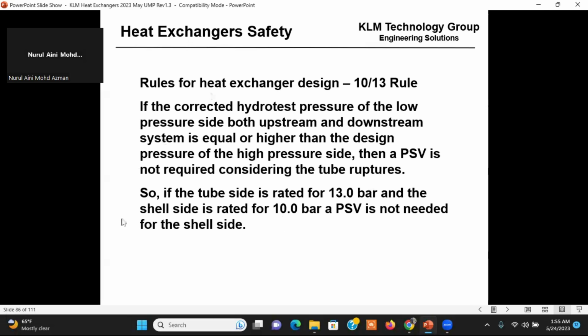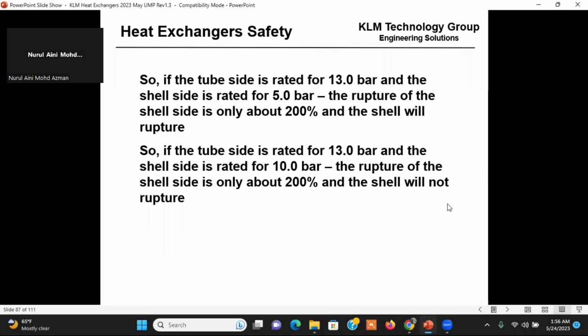Okay. So in general, I always try to follow the 10/13 rule, where if the tube side's rated for 13 bar, the shell side's rated for 10 bar. All right. So let's look at an example. If the tube side's rated for 13 bar and the shell side's rated for only 5 bar, and the rupture of the shell side is about 200%, if this 13 bar tube ruptures, I'm going to go into this 5-bar section, and I got the potential to rupture the shell because the shell's only rated for about 200%.